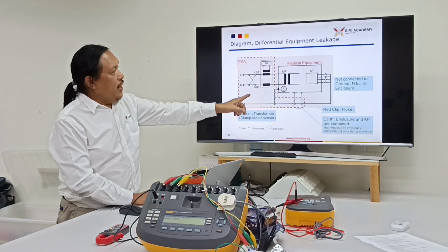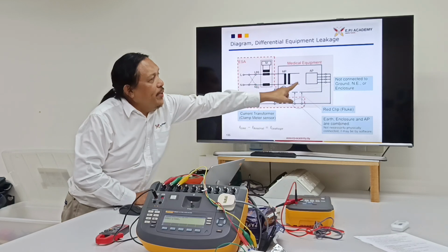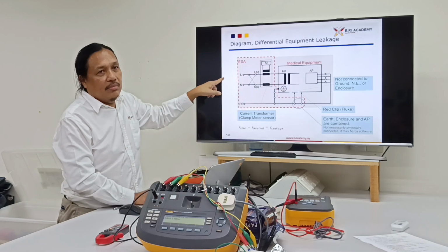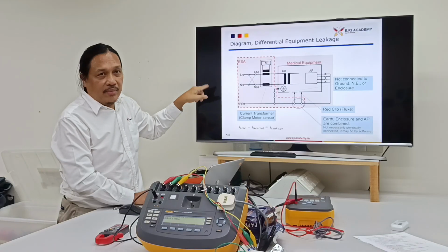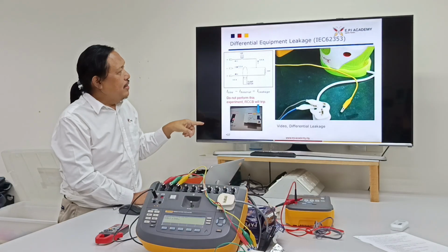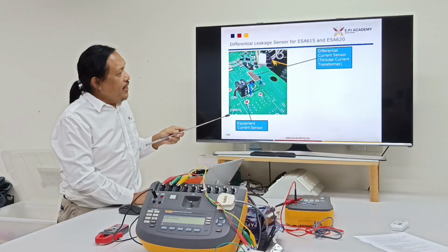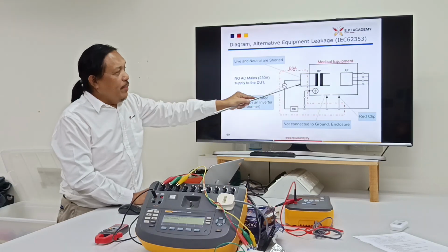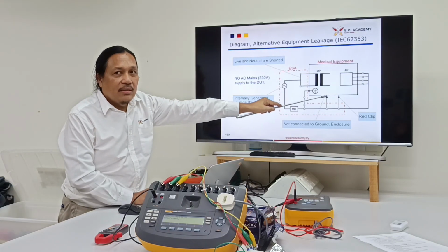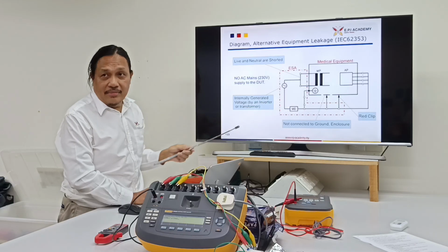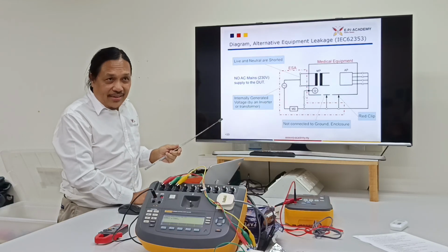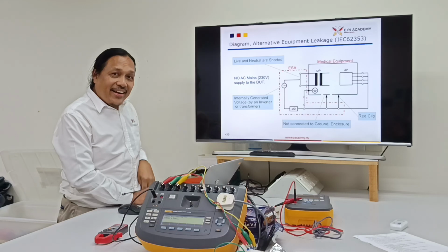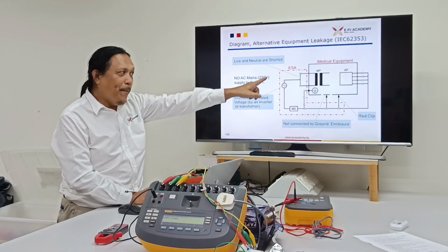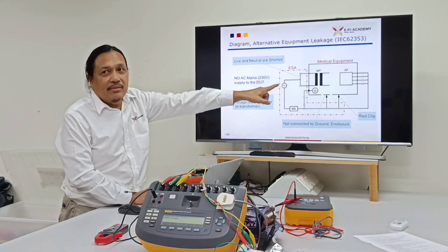So for the direct method and the differential method, the power of the medical equipment will come from the mains. Analyzer. The mains, right? The mains. Okay. For the alternative method, the power of the medical equipment is provided... where is it coming from? Analyzer. Alternative: none. No power for the medical equipment.